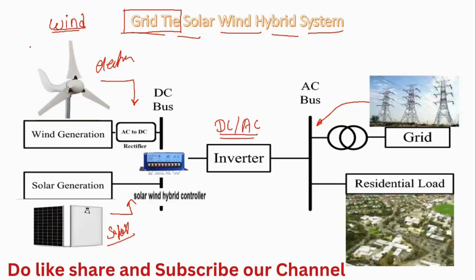The turbine generates power by absorbing the kinetic energy, and AC power is generated because at the back of the turbine there is a generator, or we can say an alternator. In the alternator, when the rotor rotates, three-phase power is generated in AC format. We have to convert this AC power into DC power because solar energy generates DC electricity. To combine both powers, from the wind and from the solar, through common DC bus bars, we require AC to DC rectifiers for the wind turbine.